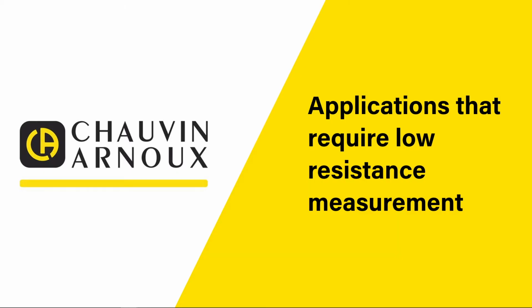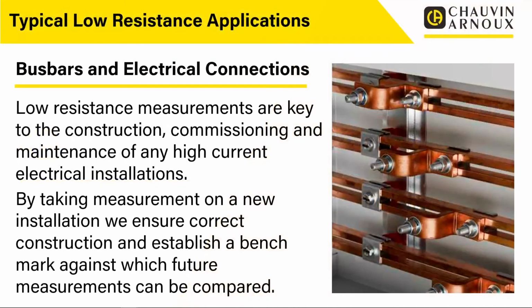Now let's take a look at some typical applications that require low resistance measurement. The first one we're going to talk about here is busbars and electrical connections. Low resistance measurements are key to the construction, commissioning and maintenance of any high current electrical installations.